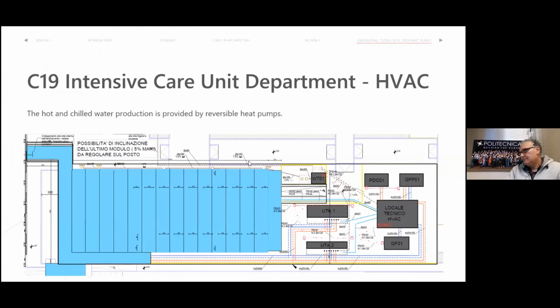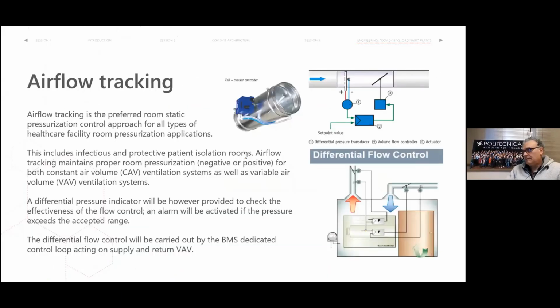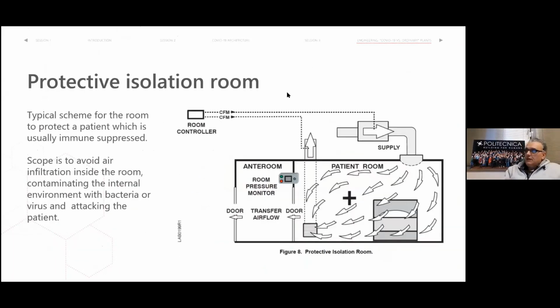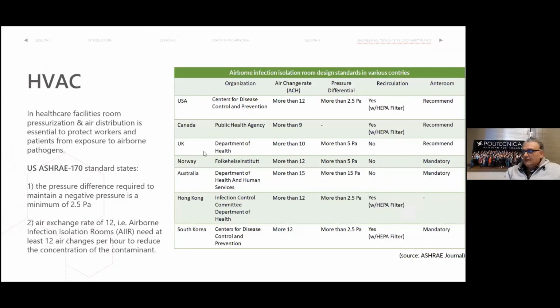Yes. Okay, so I start from the beginning because I want to show you one thing. As you see here, the HVAC standard, the United States standard, is 12 air changes per hour. What I understand from the question is that an under-designed isolation room means you probably do not have enough flow rate, or you might have problems with cracks in the envelope or something like that. So this is what I expect could be defined as under design, because you have an existing hospital, an existing situation, and you have to work with that. As you see, it is not strictly necessary to have 12 air changes per hour. You can work even with 9 or 10 according to other standards.